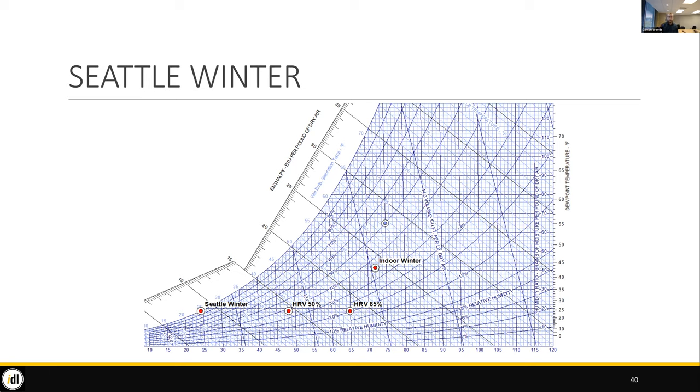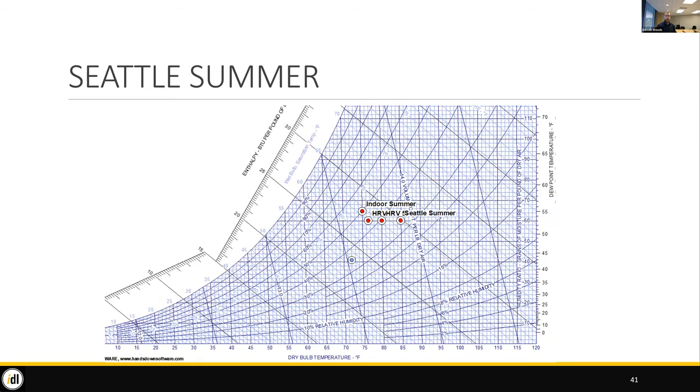You know, Seattle, you might be playing it a little bit close, but look at your design conditions. Look at what realistically is gonna be your design conditions, not just stacking on all those coincidental loads and considering the absolute worst scenario, but the reasonable coldest scenario. I was browsing today and you can actually see, as Urban Heat Island takes effect from 2009 to 2016, the ASHRAE climate data has upped by a degree or two. So make sure you're using the latest, because that might take you within a few degrees of your indoor air, and that means you no longer need that supplemental heating.